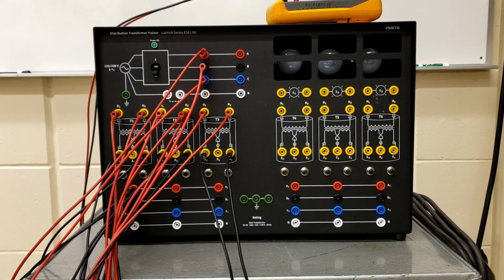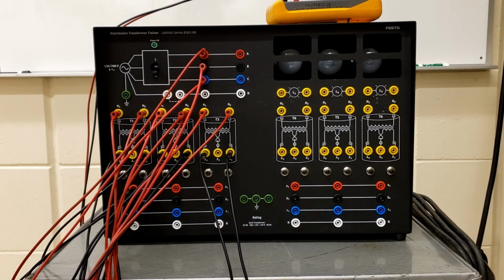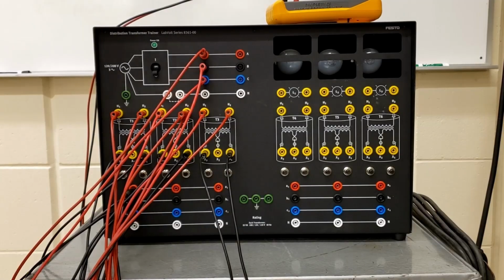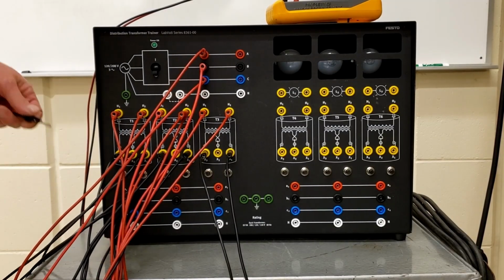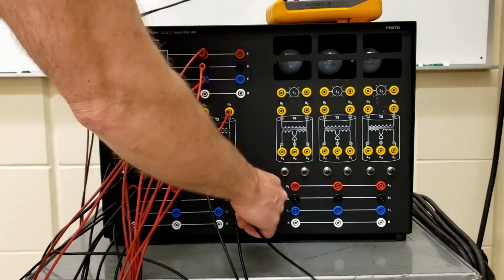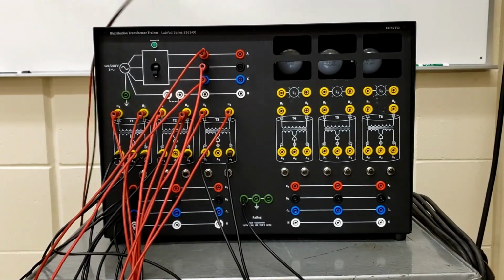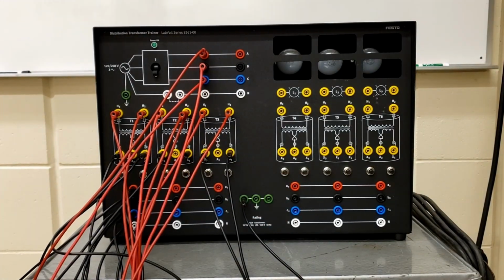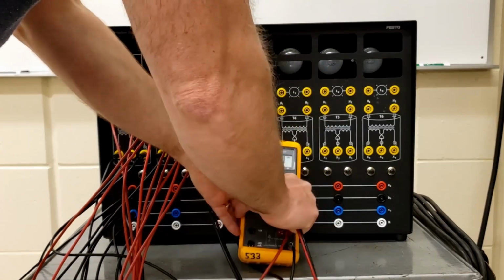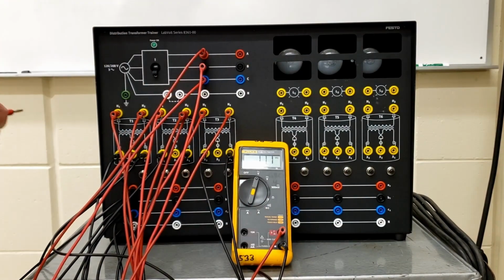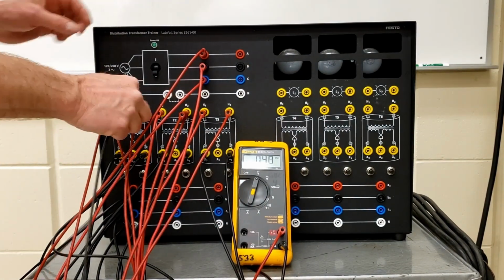Turn the distribution transformer, turn the voltage between terminals H1 and H2 of the transformer. So we're going to look at H1 and H2. What I neglected to do again is bond X2 to ground here, let's do that. And the first thing we're looking at is the voltages on the primary side, between H1 and H2.